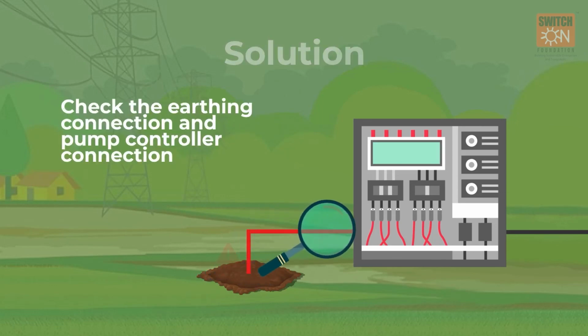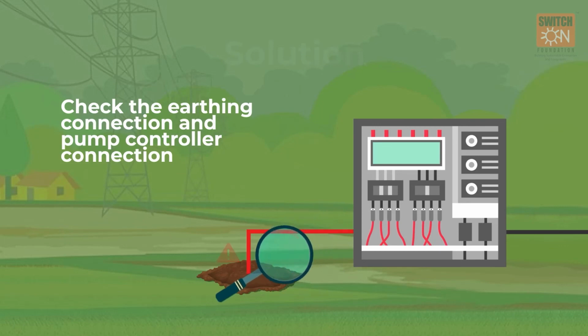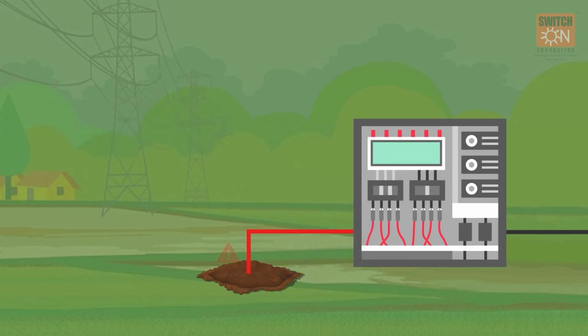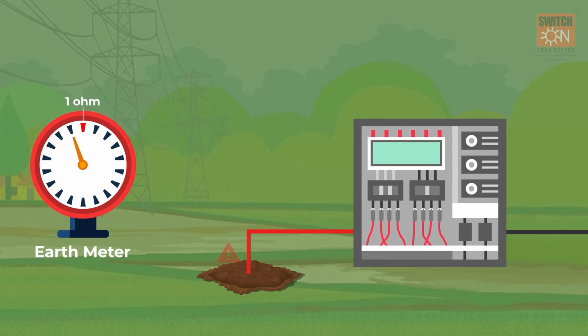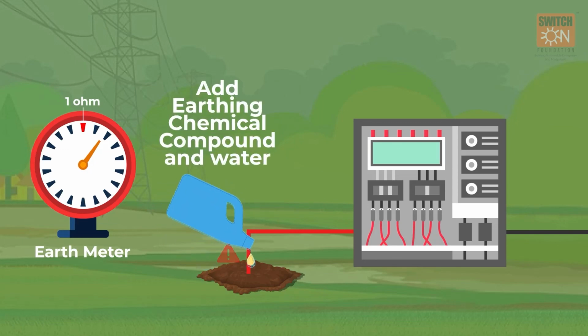Second, check earthing connection, that is, whether the earth wire is properly inserted in the ground and also connected to the pump controller. Third, check the earthing using an earth meter, and if the reading is more than 1 OHM, add more earthing chemical compounds and water till the reading reaches below 1 OHM.